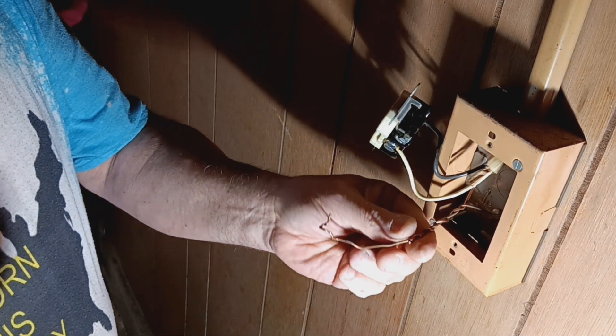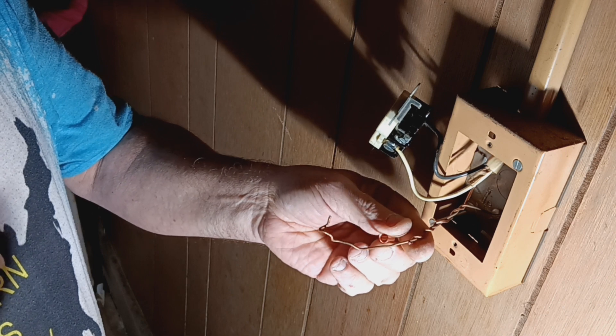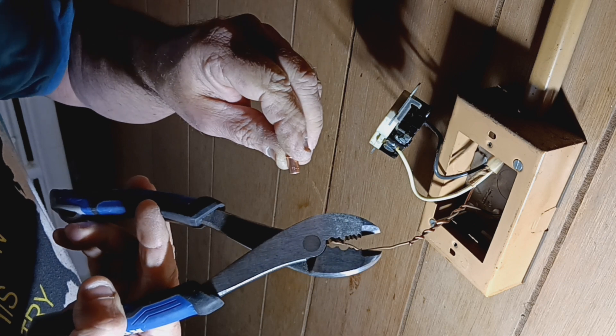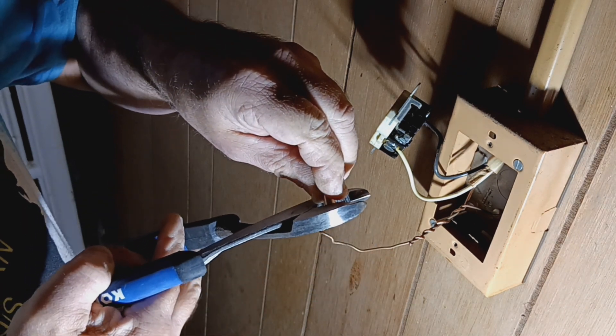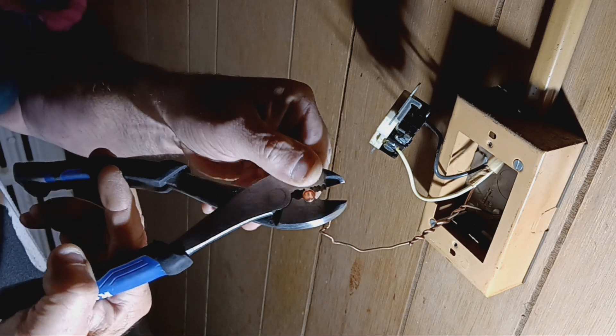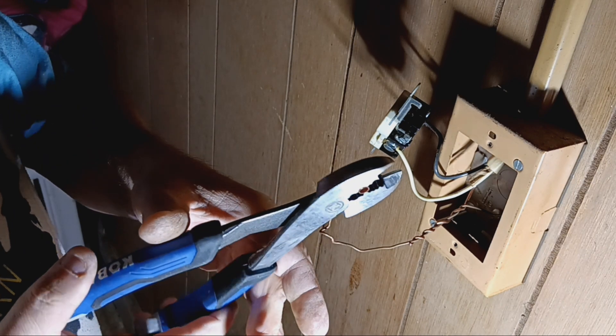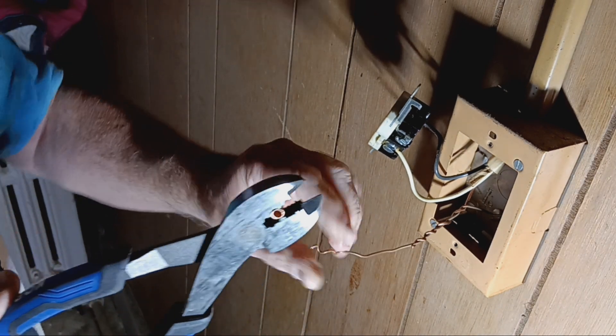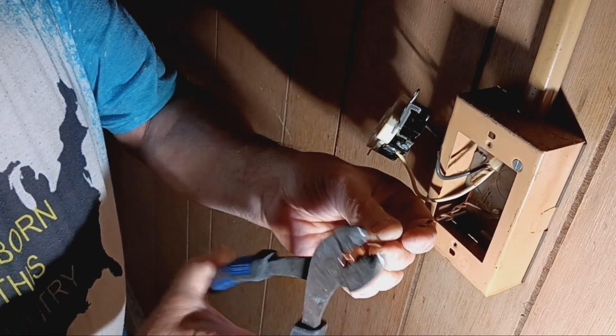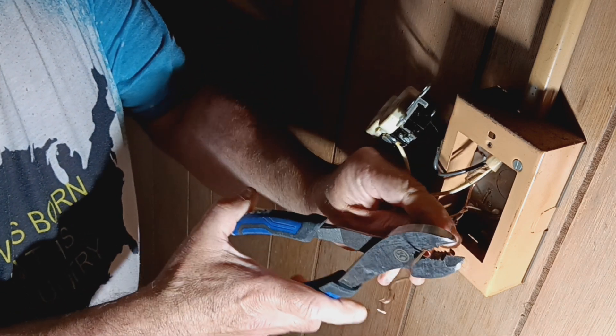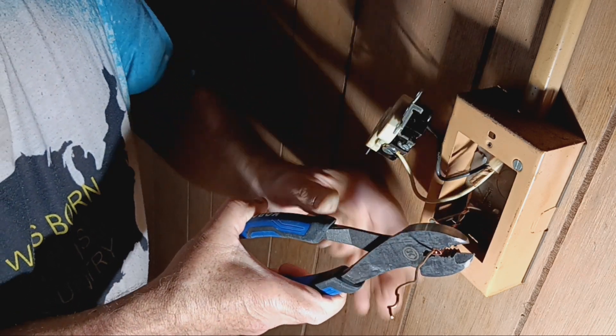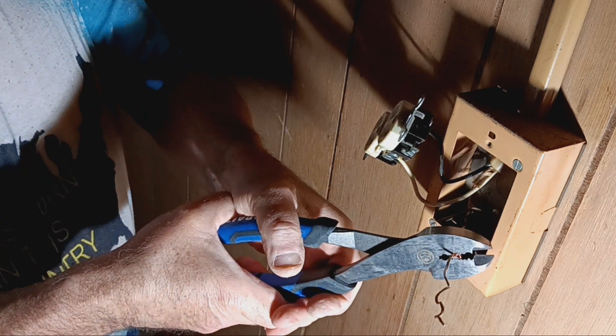Even though these are twisted counterclockwise, it's probably going to be okay since it's just going to be used with a crimp sleeve. But if it was going in a wire nut, I would undo it and twist them clockwise. So you take your crimp sleeve, you put it in your crimper like that, and I'll show you the other side. Bring it in like this until I see the second wire there. I'll squeeze it snug so it looks like that.